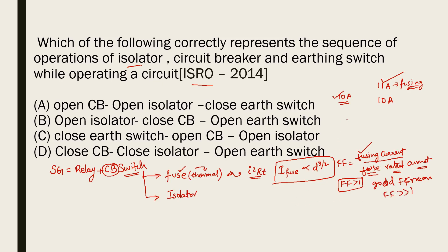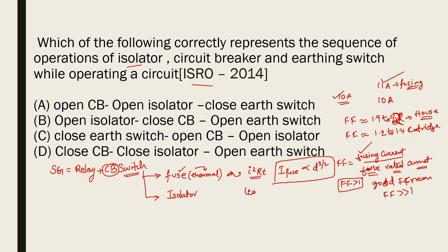For normal fuses used in house wiring applications, the fusing factor is around 1.9 to 2. For high-capacity fuses such as cartridge fuses, the fusing factor is around 1.2 to 1.4. The fusing element material commonly used is a combination of lead and tin — lead 63% and tin 37%. By varying the percentage of lead, we can vary the capacity or fusing current of the fuse.